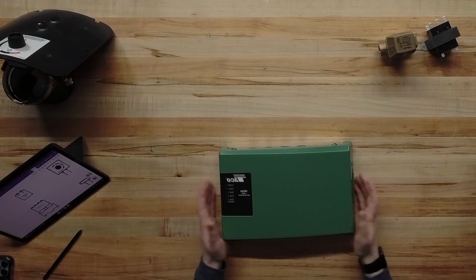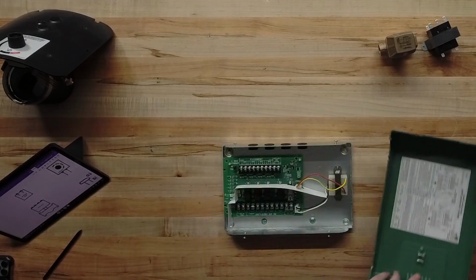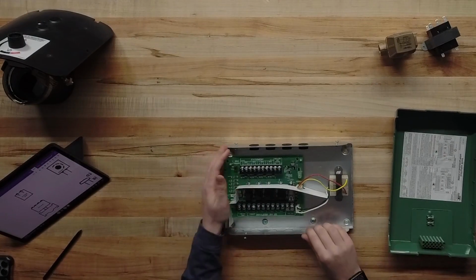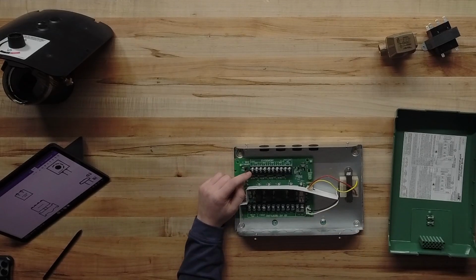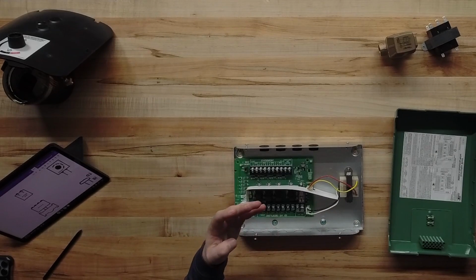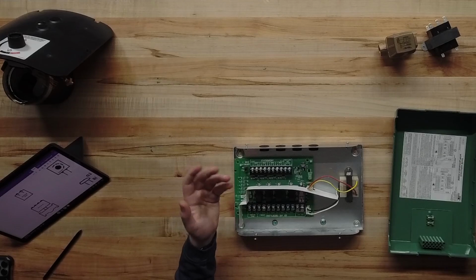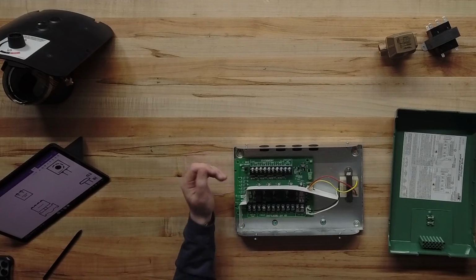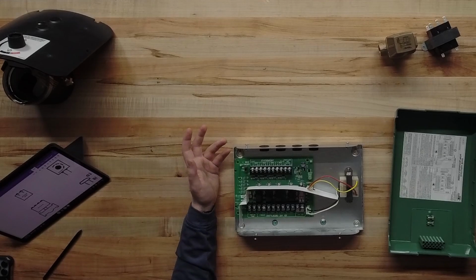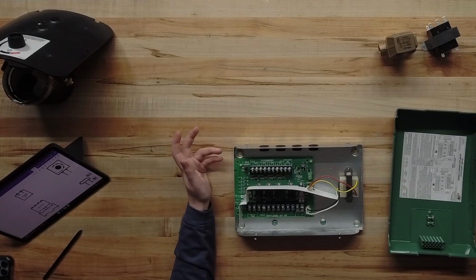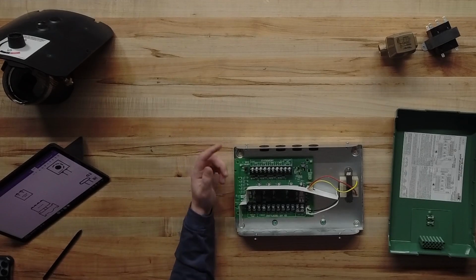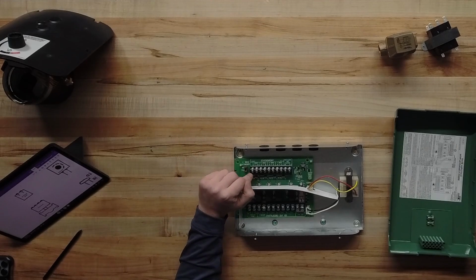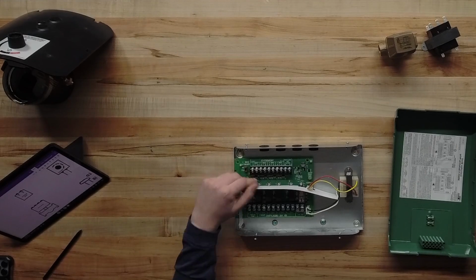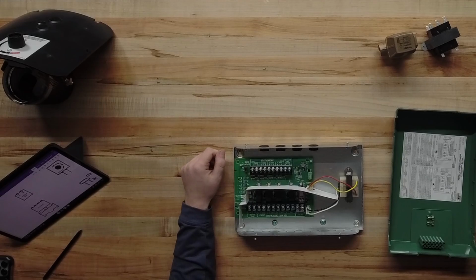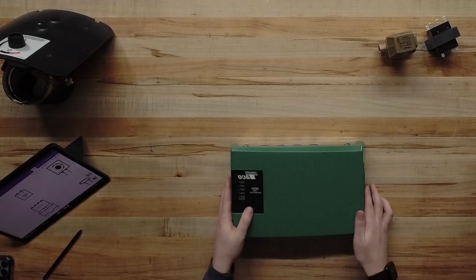On the table here, I have a Taco SR504, a very common four-zone relay out there. If you were to open it up right on the top side, you'll have your four zones. The fourth zone is your priority zone. It's very important to mention that you always want your hot water maker to be your priority zone. You need that to get heat efficiently and be the only zone getting heat. That way you get the recovery you're expecting from your Boilermate. So those two Aquastat wires would hook right up into your TT right on top here for zone four, and then you'd be good to go. Very straightforward.